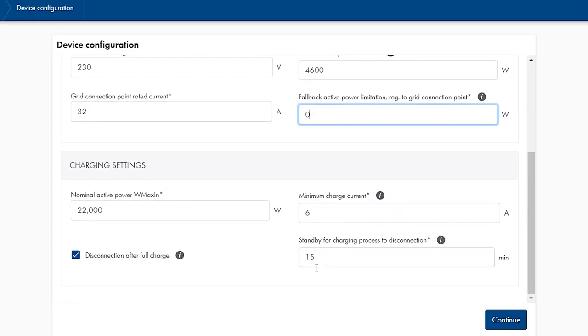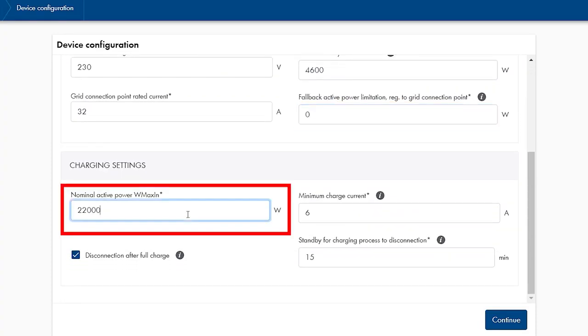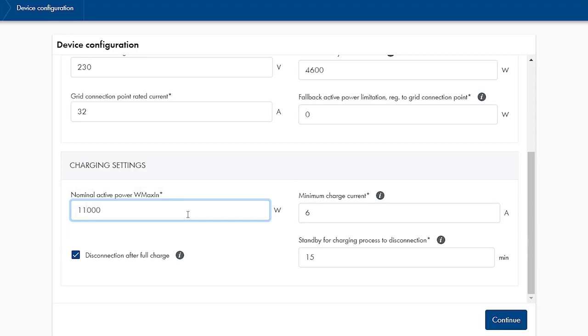The maximum charging power of the SMA EV charger can now be limited. Enter any value lower than the rated power. I choose 11000W here since in this case there is no need for approval by the grid operator in Germany.